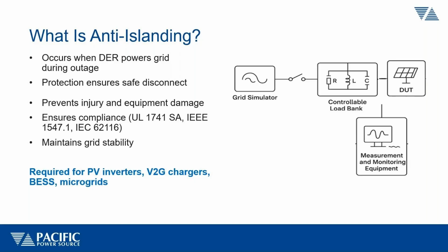So these standards are controlled by states and regulators as well as utilities, and there are some standards that apply to this. Some examples are listed here: UL 1741 or IEEE 1547, or IEC 62116 for Europe. They all have a similar objective, which is to verify that a PV inverter or any inverter that is connected to the grid has the ability to detect an anti-islanding condition, a condition of the grid disappearing, and disengage or disconnect when that happens.